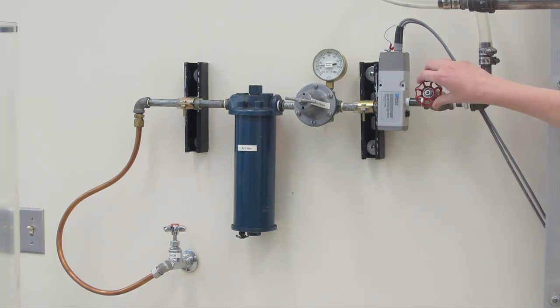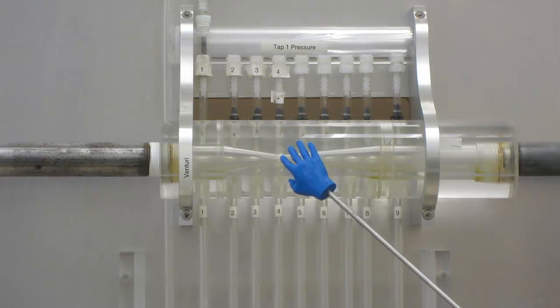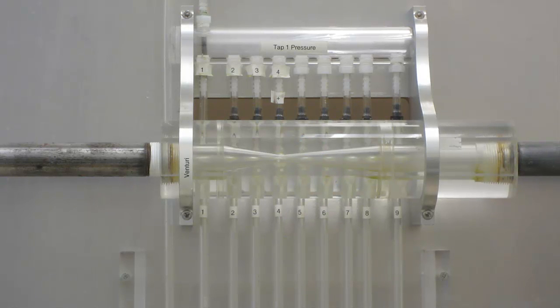As you do this, flow is going through the pipe into the Venturi shown here. The Venturi tube has pressure taps along its length, as you can see. These pressure taps are wet manometers.